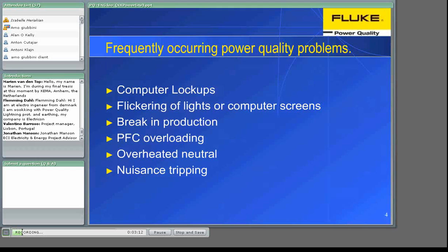Frequently occurring power quality problems. Computer lockups. A lockup occurs when the PC appears to freeze. Causes can be the system itself, for instance an obsolete operating system, or voltage variations generated by parasite currents flowing along the line impedance between devices and grounding, affecting the low voltage signals, typically 5 volts, used by IT devices. The flickering or flicker effect is nothing else than the voltage variation which causes nuisance light flashing. An excessive flicker can even cause migraine. This flicker effect will be explained in more detail further on.